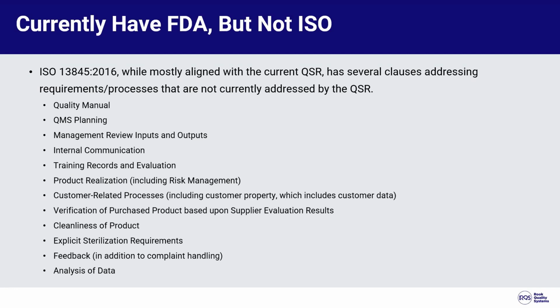ISO 13485 also covers feedback, which is more than just complaint handling. So you have good feedback, you have bad feedback, and you also have complaints, which is a subset of the bad feedback. So make sure that you are updating your quality management system in order to capture all feedback and assess all feedback, and then analysis of data, which typically ties into management review, but also takes into account all of your QMS processes, your quality objectives, the feedback you've gathered, any other post-market information you have available, and then tying that all together to report to management.